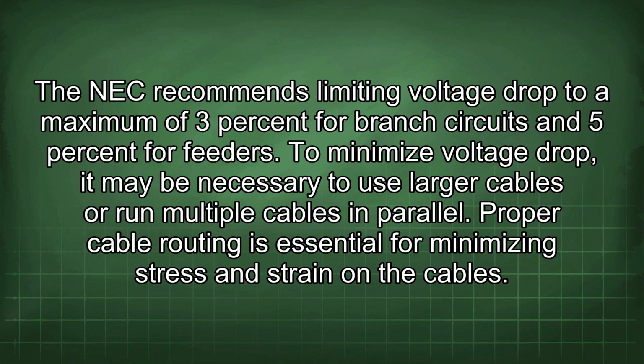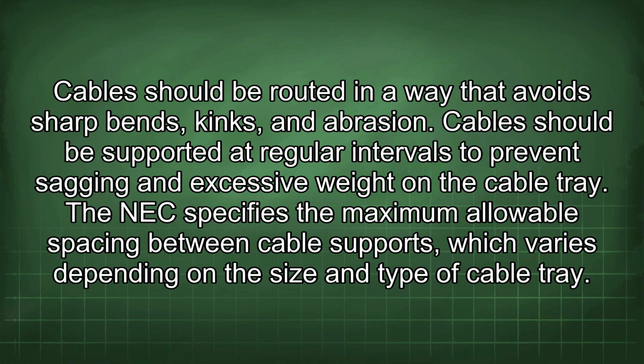Proper cable routing is essential for minimizing stress and strain on the cables. Cables should be routed in a way that avoids sharp bends, kinks, and abrasion. Cables should be supported at regular intervals to prevent sagging and excessive weight on the cable tray. The NEC specifies the maximum allowable spacing between cable supports, which varies depending on the size and type of cable tray.